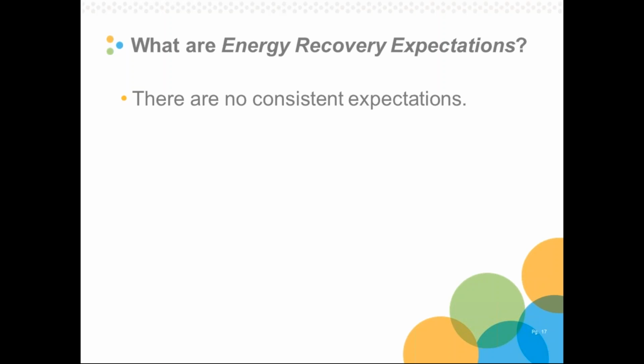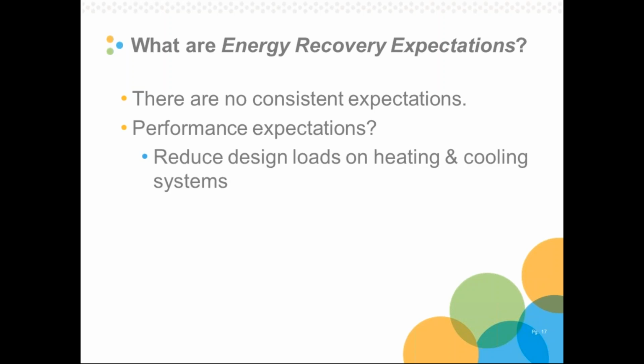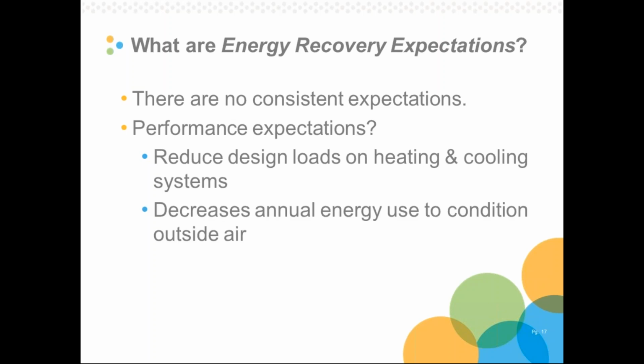Now, I know there's a lot of engineers with us today, and they might dispute this. I think we all have some performance expectations in mind when we talk about energy recovery systems. For example, if we follow the ASHRAE and the design literature, we know that we often implement energy recovery to reduce design loads on heating and cooling systems. Consequently, we expect that when properly implemented, energy recovery systems are going to reduce the annual amount of energy we use to condition outside air. But I can say this, again, in hindsight from this study, and based on the expectations that people cite, if ERVs are missing their expectations, it is not for performance-related issues. And specifically, it's not for these performance-related issues.